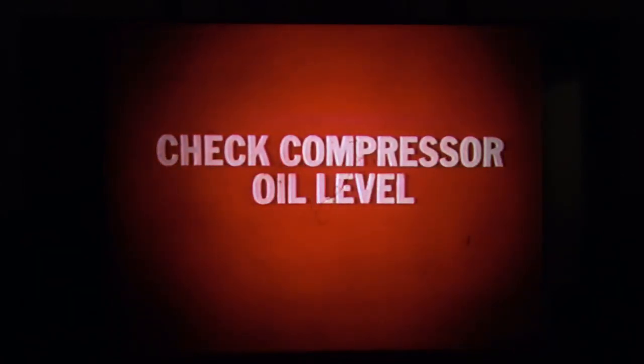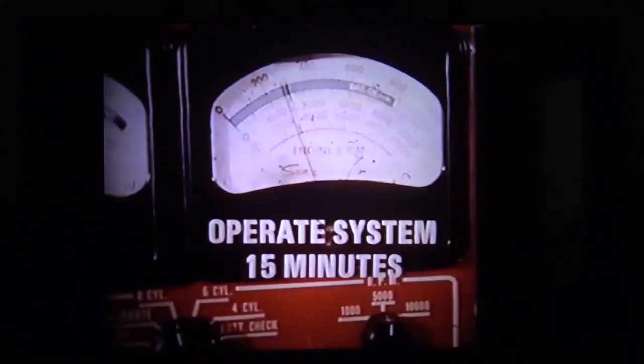Because some of the oil from the compressor sump is picked up and circulated through the system with the refrigerant, the crankcase oil level must be checked. With the engine operating at 1200 to 1400 RPM, operate the air conditioner at maximum cooling for approximately 15 minutes.